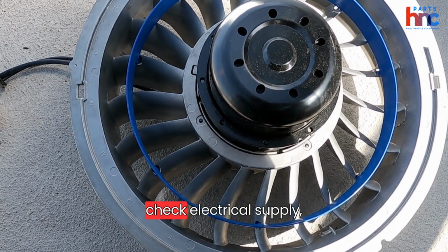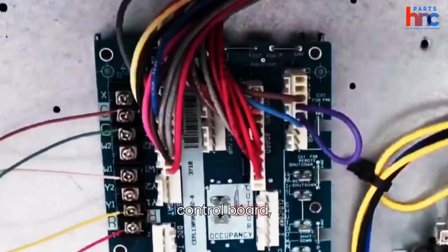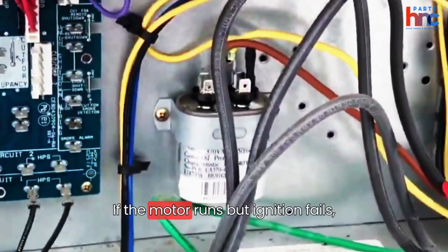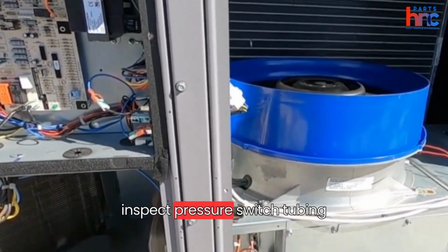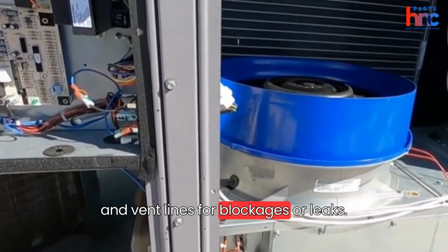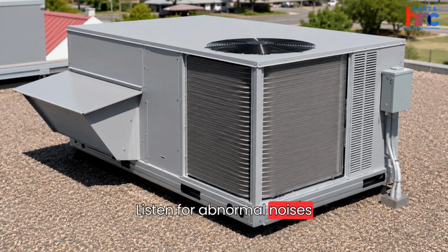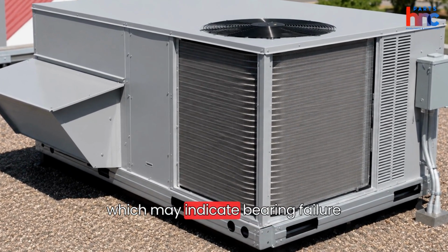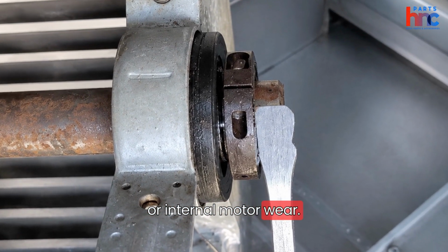If the motor does not run, check electrical supply, wiring, control board, or capacitor issues. If the motor runs but ignition fails, inspect pressure switch tubing and vent lines for blockages or leaks. Listen for abnormal noises like grinding or rattling, which may indicate bearing failure or internal motor wear.